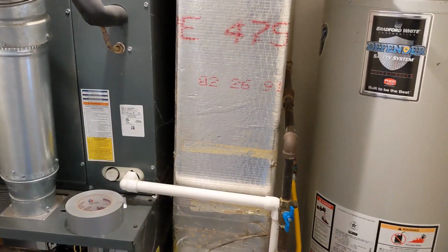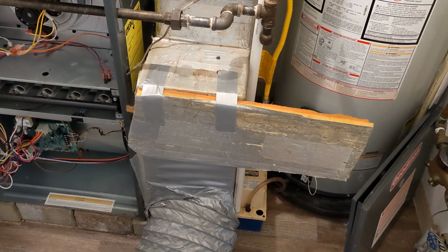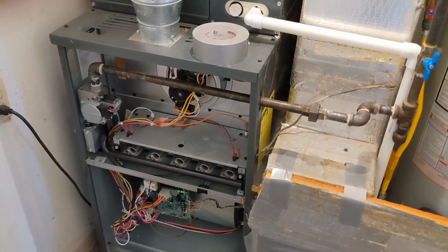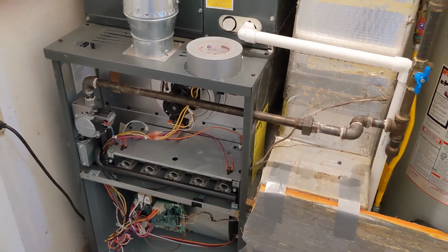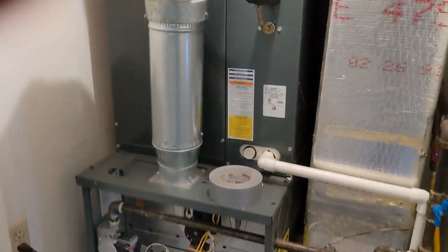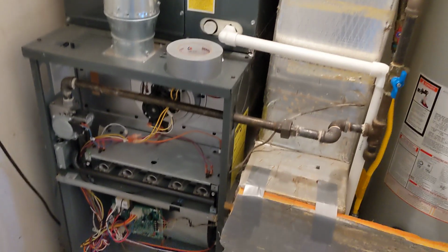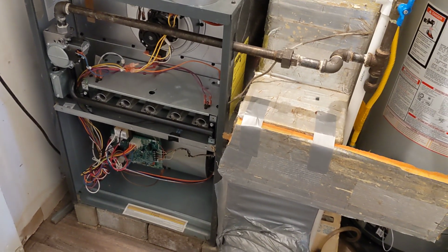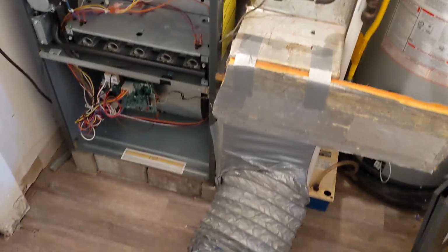would then recontaminate your supply side that you already cleaned. So you always start on the return side, clean that, remove all of the dust, dirt, and debris, then go to the unit, clean the coils, fans, motors, things like that, and then go to the supply side. That way everything stays cleaned. You don't waste time or energy cleaning something and then it gets recontaminated.